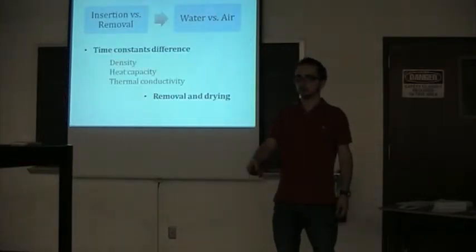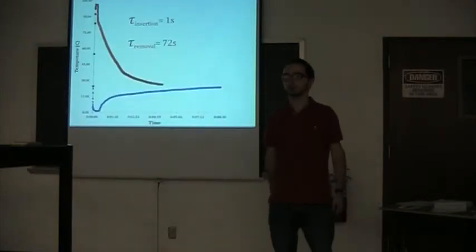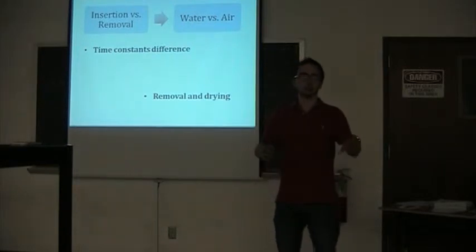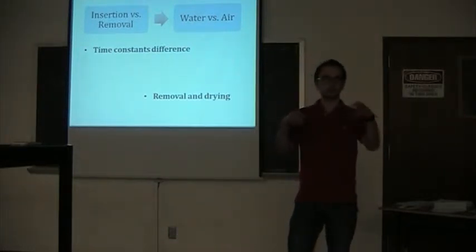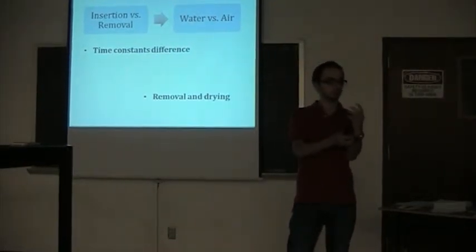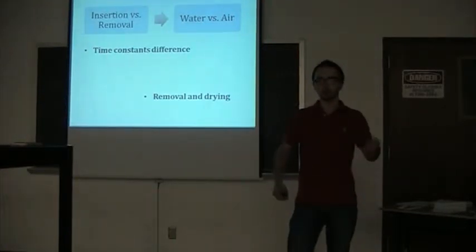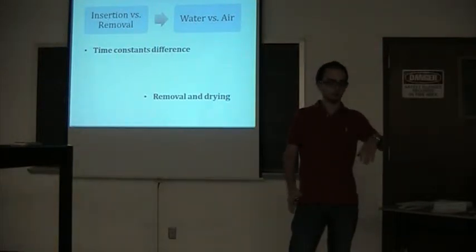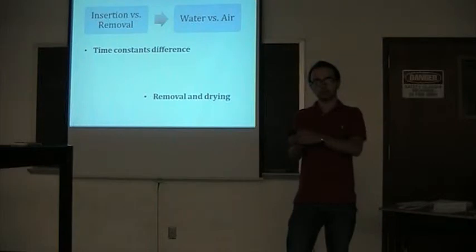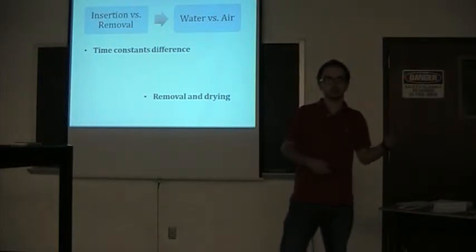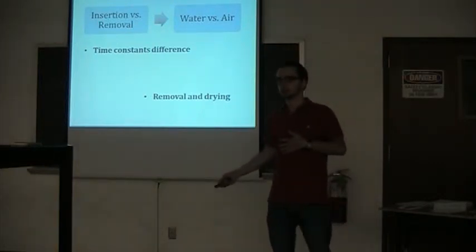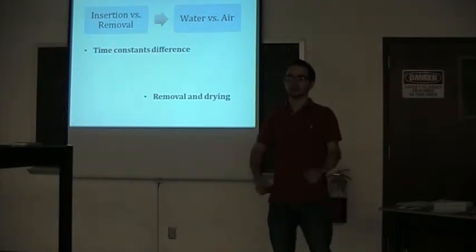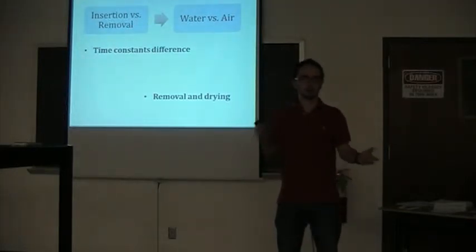From what we can see here, our time constants are going to be very different from insertion and removal. When you put the thermocouple in the water, you have a lot smaller time constant than when you pull it out. And you have to ask yourself, why is this different? Well, the main difference here is water versus air.